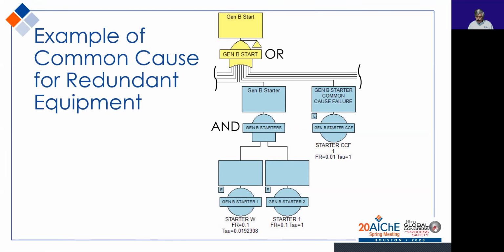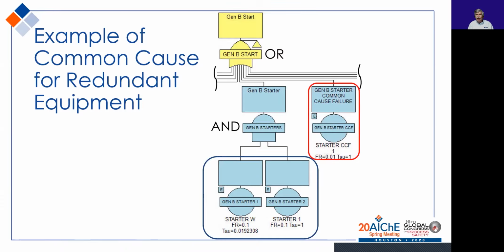So generator B has starter 1 and starter 2. If one doesn't work, the other one should be able to start the genset. However, because of common cause, both starters may fail to start the generator for the same reason. So we have generator B, common cause. The failure rate for the common cause, FR, is 10% of the failure rate for a single starter. We have a similar tree for the 2 batteries for each generator.